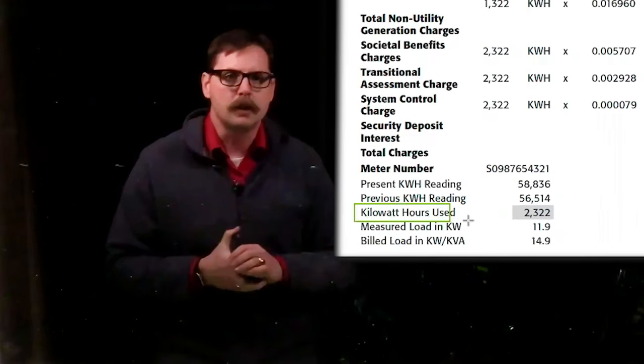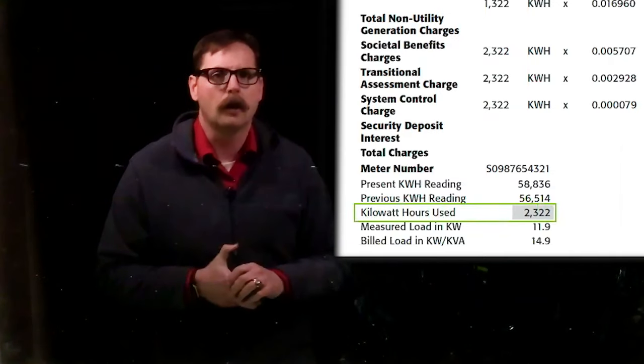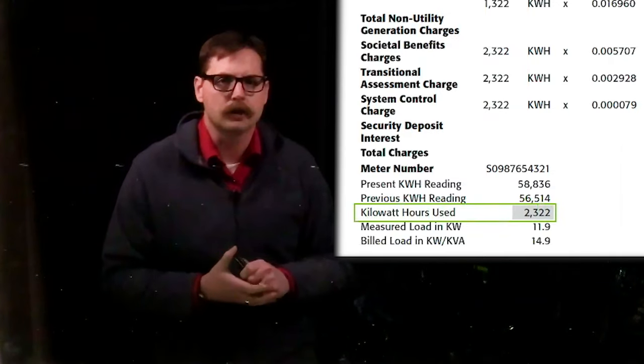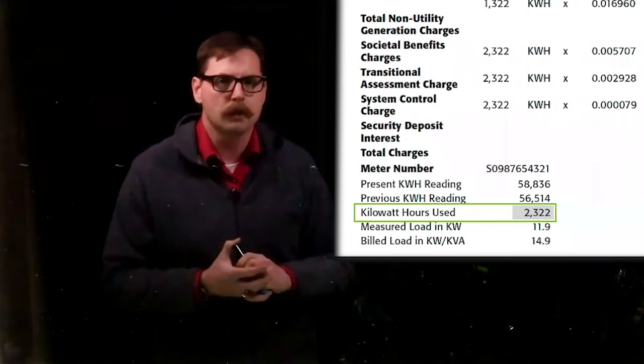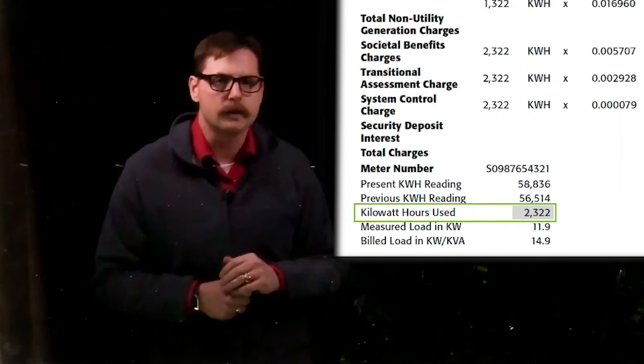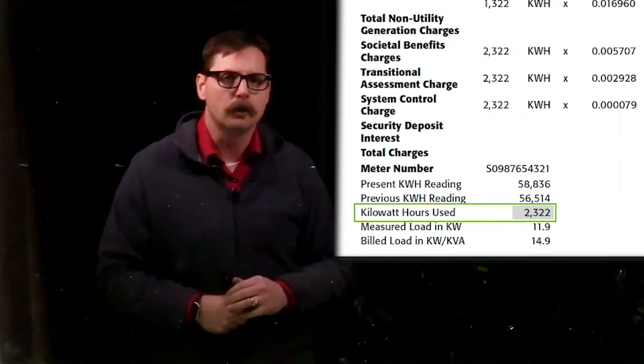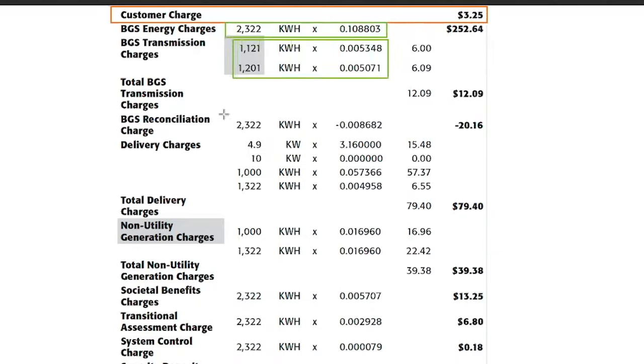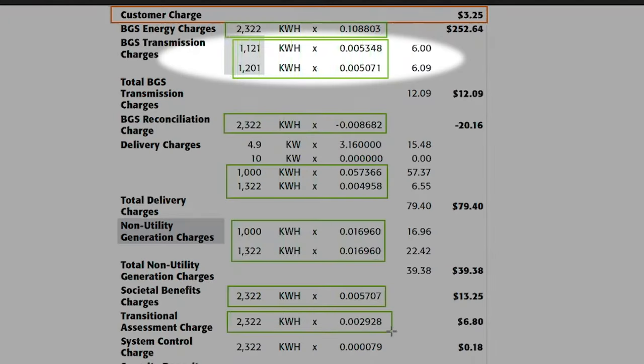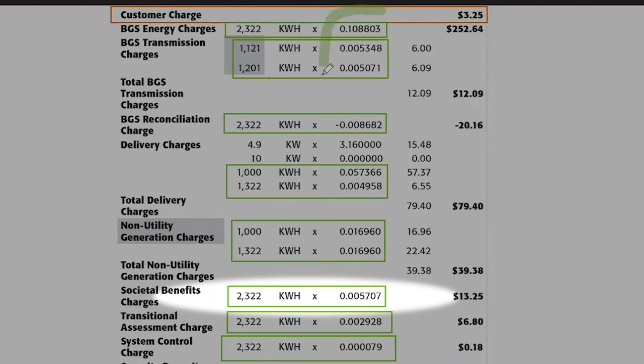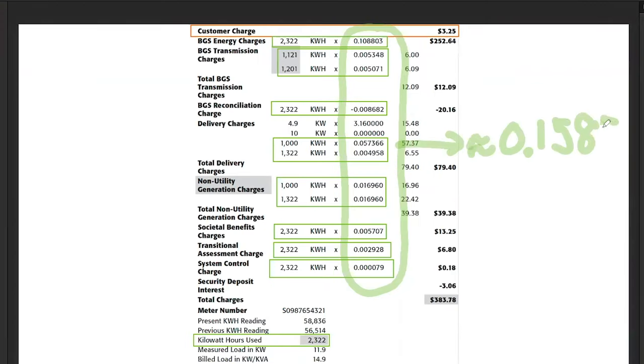If we're thinking about the next charge, which would be the usage charge, remember those are charged per kWh. So first, let's try to identify how much electricity in kWh we use during this billing period. And so if we look at this bill, it says that we use 2,322 kWh during the billing period. And then we can look down that bill and identify all of the places where we're charged per kWh. Now some of them are broken apart, maybe because they had different suppliers. If we add all those up, we get 15.85. So basically 15.85 cents per kWh is our usage charge.